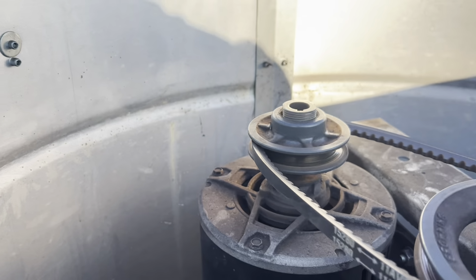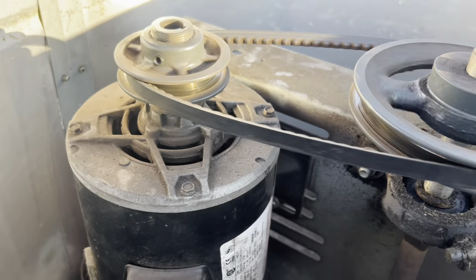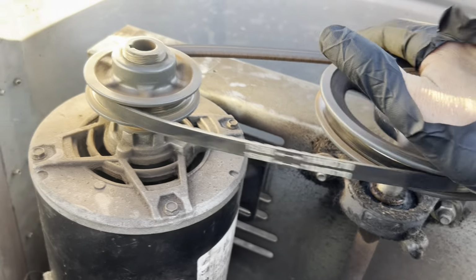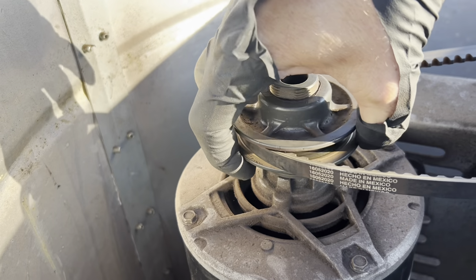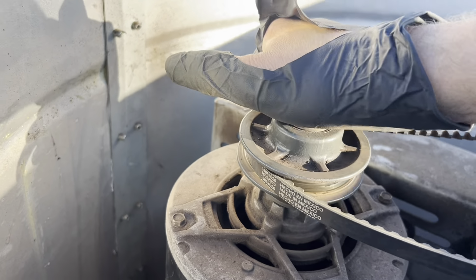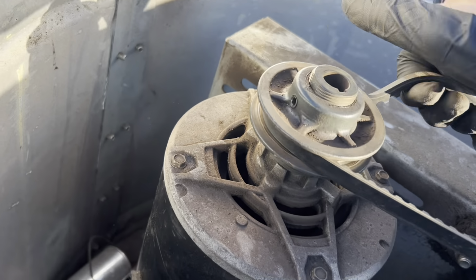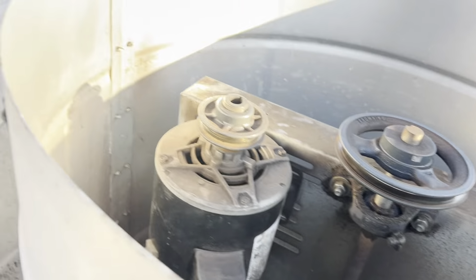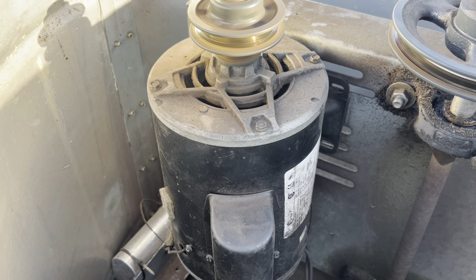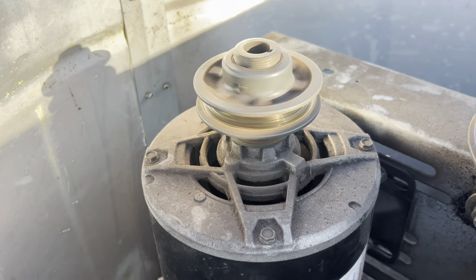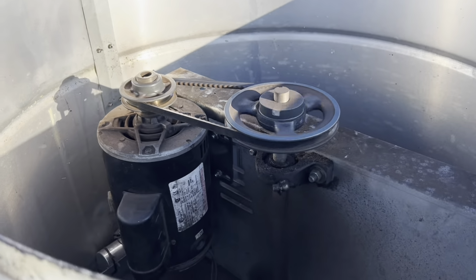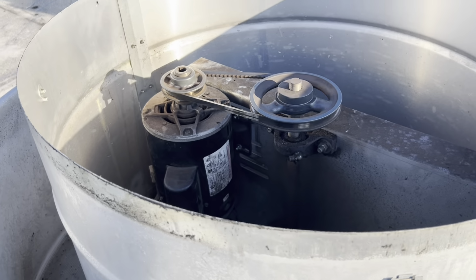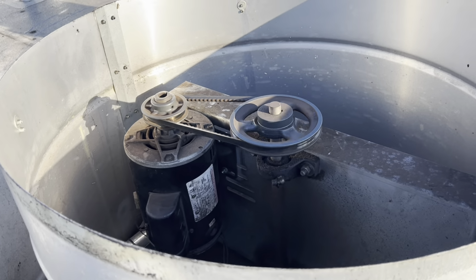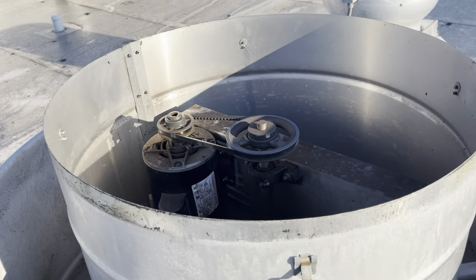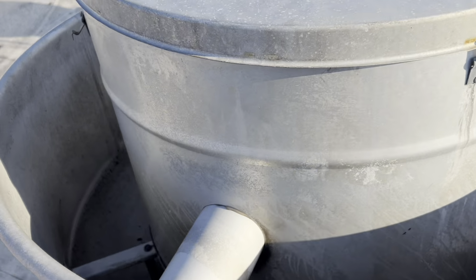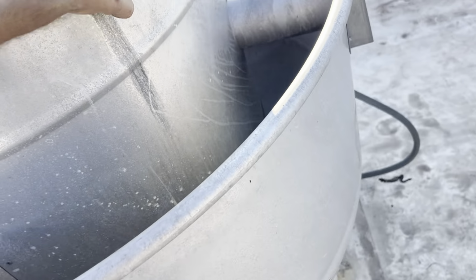I don't know if you saw it, but look, this exhaust hood, it's not what I'm here for. The belt's super loose, but that's not the problem. The problem is the motor's broke loose on the inside, and it has nothing to do with the fans. If I fire up the motor, shaft move, uh-oh. All right, bringing her up to speed actually gives the motor the best chance. I'm running the least amp draw right now, and I'm running under amps. So she's moving some air, she's good, but I wouldn't shut this thing down. I'd leave this thing running until we get that motor replaced.